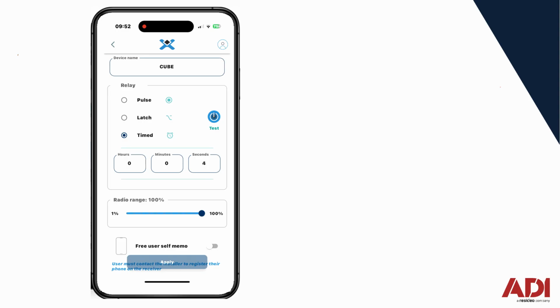And if you want to, you've got that button there that says test. I don't know if you can hear the relay if I try it. Let's try. The relay pulsed for 4 seconds. And there we are. That's the advanced relay settings for the Cdvi CubeKit.